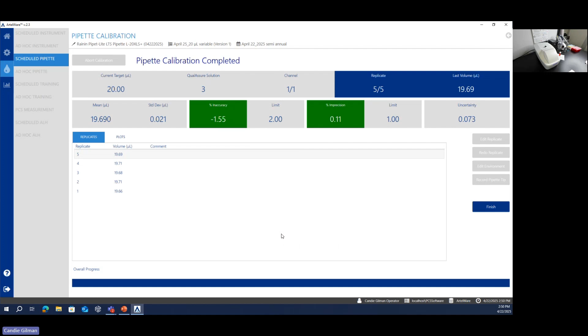Now, the moment I select finish, my particular workflow for my pipette calibrations requires that I have a separate person review my calibration data. Now you can change that workflow in the Artel software so that the person who's calibrating is also the same person that's reviewing, one and the same. You don't need a separate level reviewer, but in my case, I do have a separate level reviewer, and that's reviewer 1. So I'm going to go ahead and select OK. And if I had the automated email notification feature of Artel enabled, that reviewer 1 will have just now received an email from the system indicating that there's a calibration report that has to be reviewed.